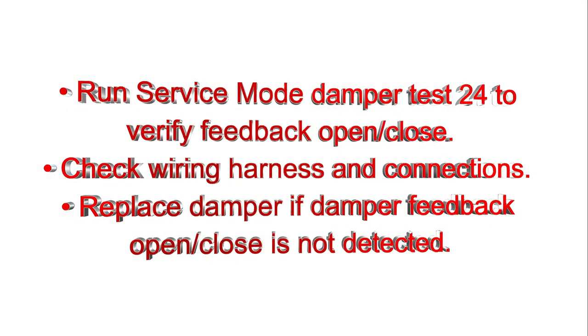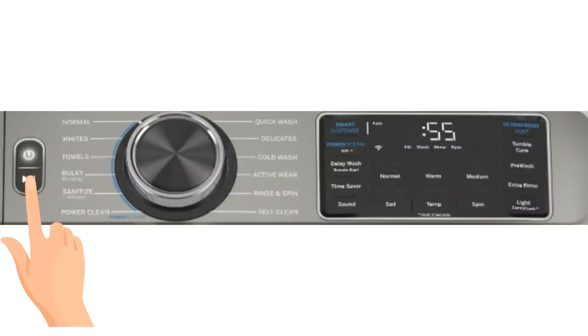Error codes 38, 39, 40, 84: vent damper. Fault is set if close/open feedback fails after 5 seconds. Run service mode damper test 24 to verify feedback, open/close, and check wiring harness and connections. Replace damper if damper feedback open/close is not detected. Test mode 24, damper. Pressing start/pause will toggle the damper state. When the damper feedback indicates that the damper is open, the soil level light LED will blink. When the damper feedback indicates that the damper is closed, the soil level extra light LED will blink.